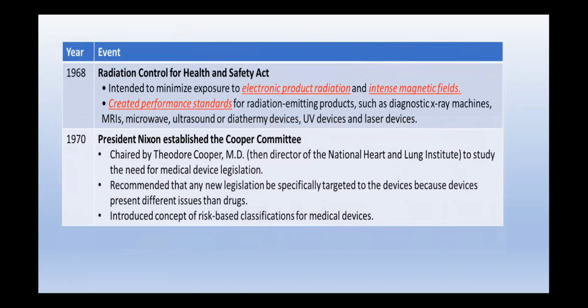In 1968, the Radiation Control for Health and Safety Act was passed, which intended to minimize the exposure of users or patients to electronic product radiation and intense magnetic fields. It created performance standards for radiation-emitting products such as diagnostic X-ray machines, MRI, microwaves, ultrasound, etc. In 1970, President Nixon established the Cooper Committee in the USA, chaired by Theodore Cooper. He recommended that there had to be new legislation specifically targeted at the medical devices industry, because the regulations then in place were not able to meet current medical device needs. He also introduced the concept of risk-based classification of medical devices.